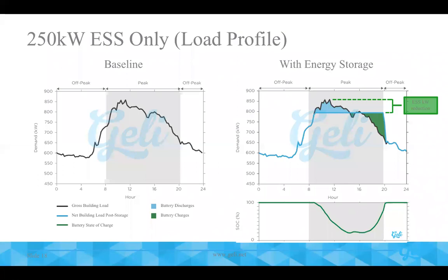Now you're saying, well, it's a 250 kilowatt system. Why does it only take it down 50 kilowatts? Well, when the battery acts on its own, it has to address peaks over a very long period of time. And this is only a 1 hour energy storage system. And so it's got a 5-hour peak window here. If you've got 5 hours of energy, you're delivering 50 kilowatts, that's 250 kilowatt hours, which is about the capacity of the battery. So batteries on their own really aren't that effective at reducing peaks for facilities that have a load profile such as this. If there's one spike in the middle of the day and everything else is flat, could be good.